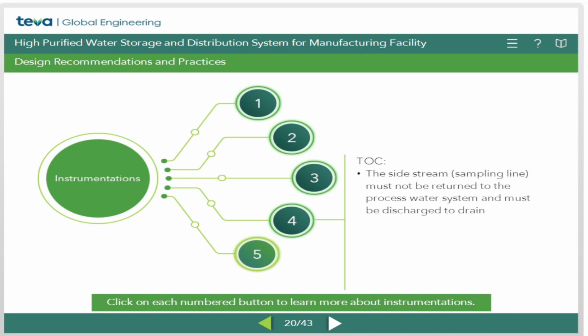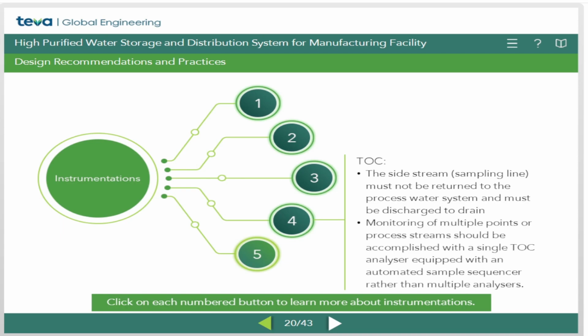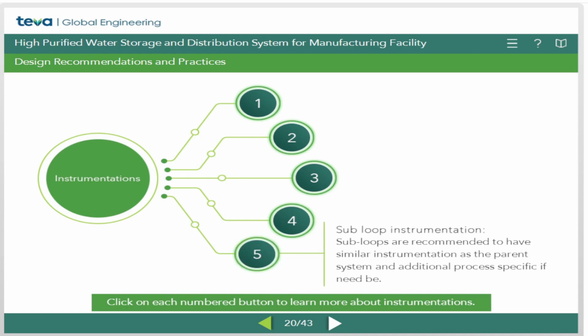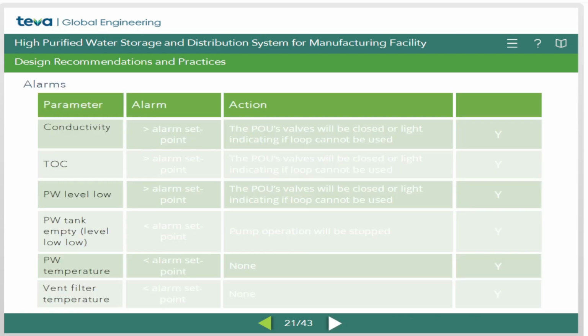TOC. The side stream must not be returned to the process water system and must be discharged to drain. Monitoring of multiple points or process streams should be accomplished with a single TOC analyzer equipped with an automated sample sequencer rather than multiple analyzers. Subloop instrumentation. Subloops are recommended to have similar instrumentation as the parent system and additional process-specific if need be. Here are the parameters for alarms and the required actions that need to be taken.